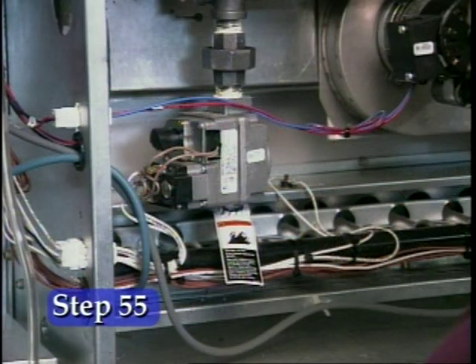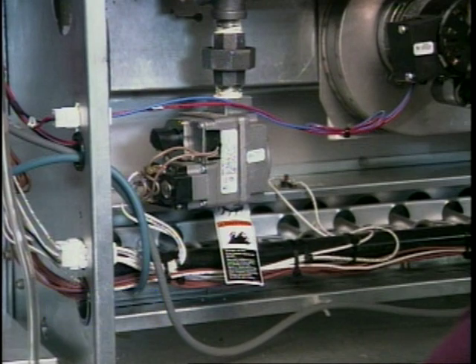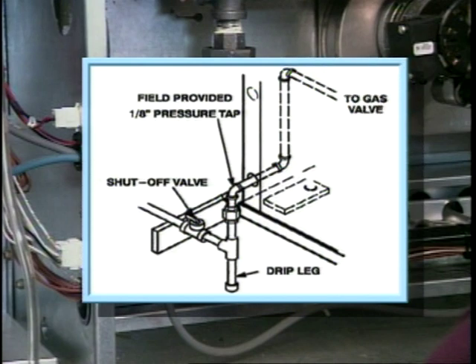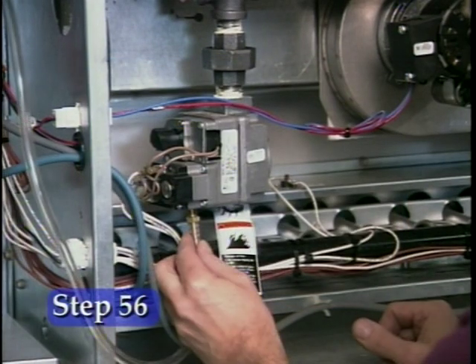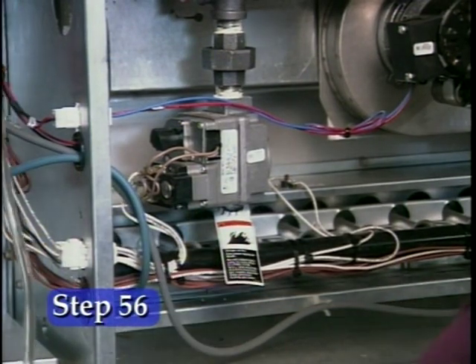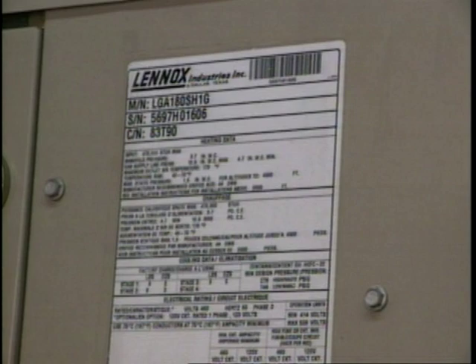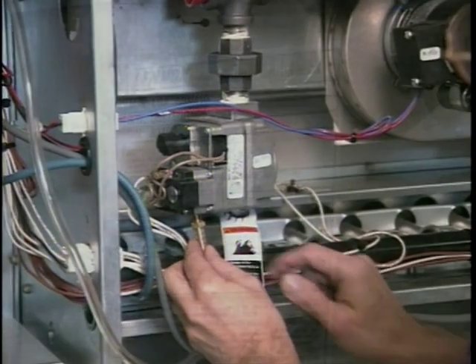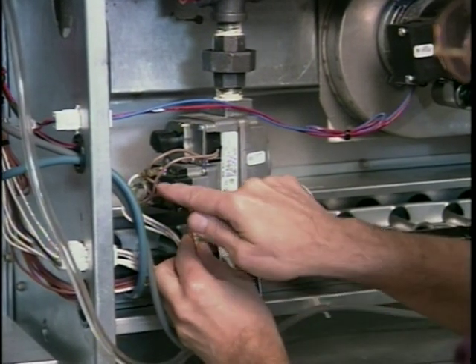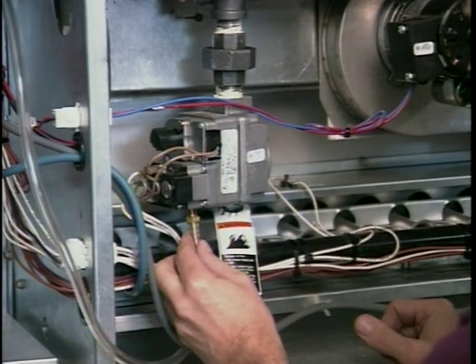Check the gas line pressure at the 1/8-inch pipe tap installed upstream of the valve. If a tap is not available, remove the cap from the drip leg and temporarily install a reducer to connect your manometer or gauge. Measure the outlet pressure of each gas valve. Check the nameplate for the required gas manifold pressure. If pressure is different from the nameplate data, adjust the valve as required.